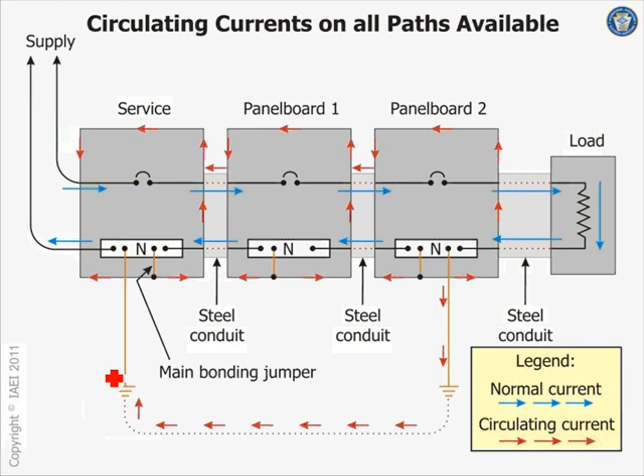Now look what happens if I send one of my friends there and they bond the neutral at multiple locations. Now your coaxial cable in this area is carrying current, because the shield of the coaxial cable could be bonded at both ends. Your water pipe is carrying current. So you can see the conduit now under normal operating conditions. This is not a short circuit, that's normal operating condition.